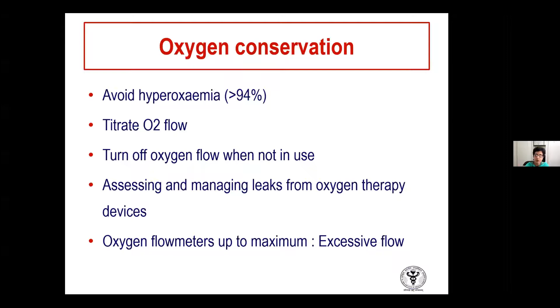But there should be some person who should be assessing and managing leaks from oxygen therapy devices at all times. Then another thing that often goes unnoticed is that when you are turning the oxygen flow meters up to the maximum, the flow meter shows 15 liters per minute maximum. But if we keep turning it, although the indicator cannot go more than 15 liters per minute, the actual flow is actually increasing. So if you keep on turning the knob, the flow is increasing, but you think that it's just 15 liters per minute. It is actually increasing, and a lot of flow is wasted like that. So one should ensure that you do not turn it to the maximum.